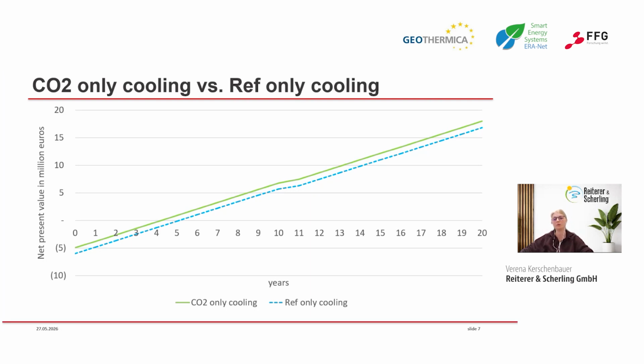However, a closer look shows that this difference is mainly due to high investment costs in the conventional system, which we can see by year 0, where we have about 1 to 2 million euros more in investment costs. The large costs are the very expensive heat exchangers.